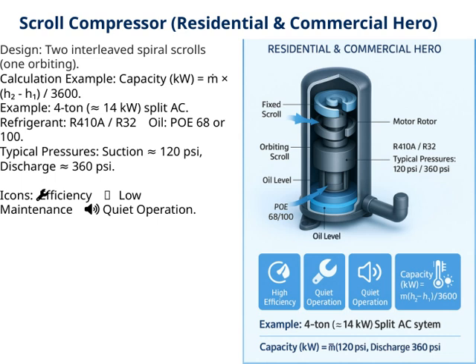For example, a typical 4-ton split air conditioner, which is roughly 14 kilowatts, uses this calculation to ensure it meets the cooling demand. The refrigerants most commonly used are R410A and R32, both known for their efficiency and lower environmental impact. The oil used in these compressors is POE 68 or 100, which provides good lubrication and performance. In terms of pressures, the typical suction pressure is around 120 psi, while the discharge pressure is approximately 360 psi. These pressures are crucial for efficient compressor operation.